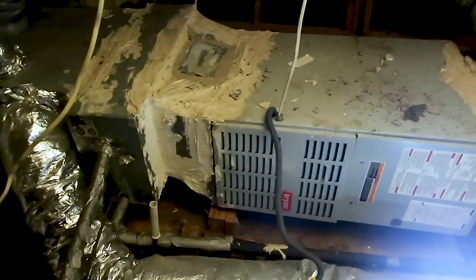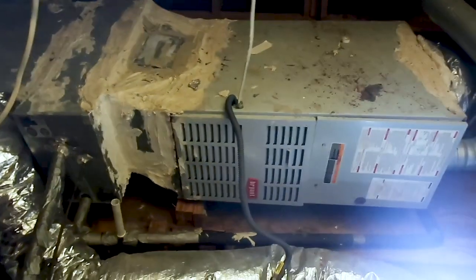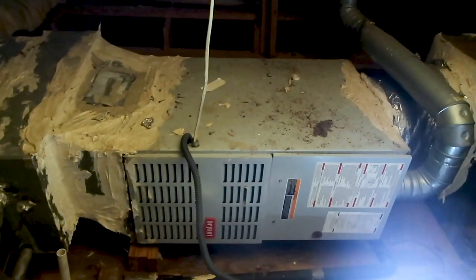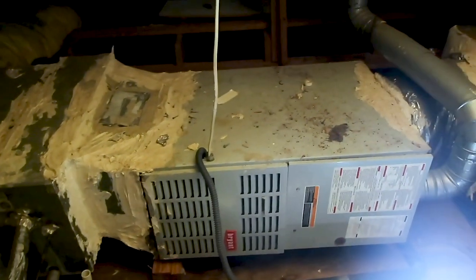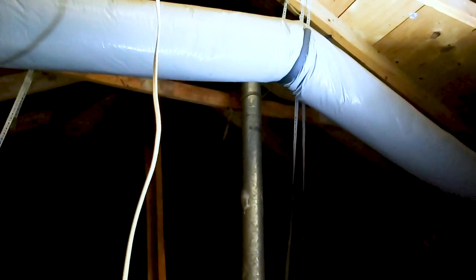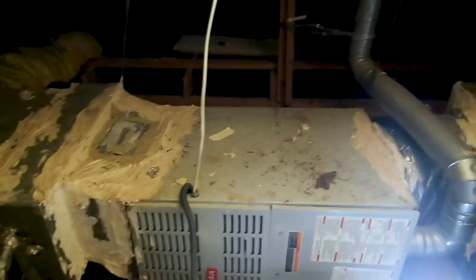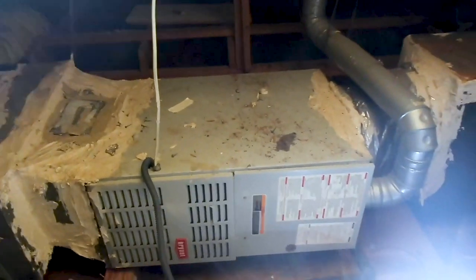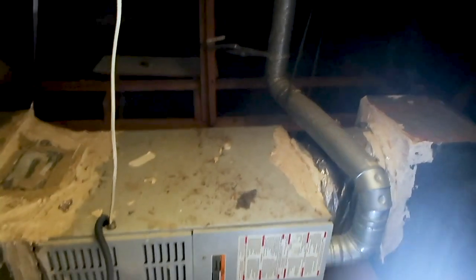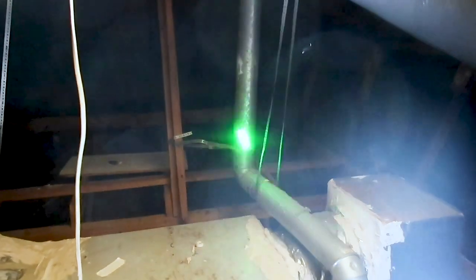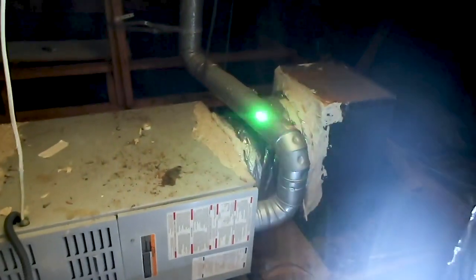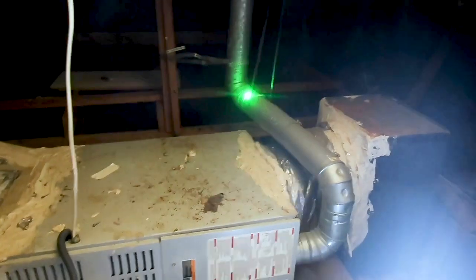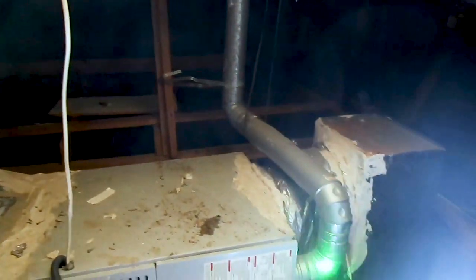So let's start up in the attic. Made it over. What I like to do first for my strategy is start from top to bottom, so I'll start with the flue. I'll make sure the flue is properly installed, that it exits out, and that it's watertight from the attic side. If you see light coming in, it's a sign that it might not be watertight. You also want to make sure the flue is connected all the way through—mechanically attached, with no separations.